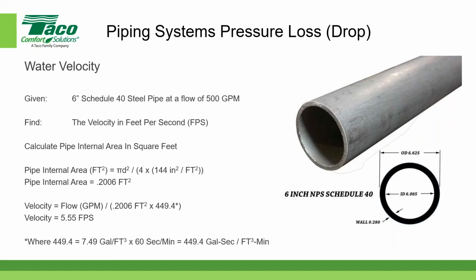So again, the velocity is equal to the volumetric flow divided by the cross-sectional area. Since the volumetric flow wants to be in cubic feet per second, and we're using the units of gallons per minute, we have to use the conversion from gallons per minute into cubic feet per second. Then if we take the volumetric flow and divide it by the cross-sectional area, that's how we find out what the velocity is. Does that help? And then we're assuming that the pipe is full, correct? Correct, yes. No air in the pipe.